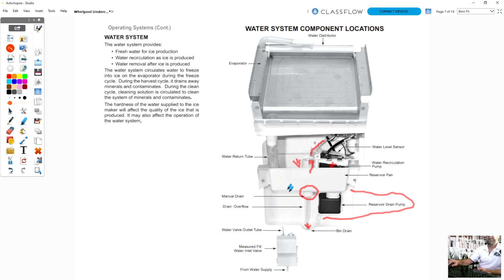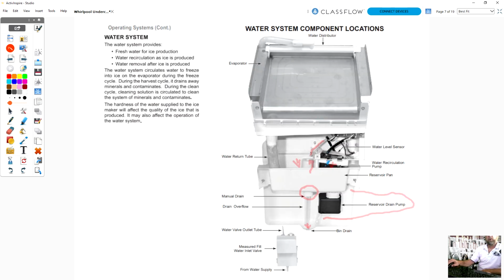If you're going to do any service to this area, you're going to have to remove the cutter grid like they're showing you in this picture here. So if you have to do the circulation pump, you have to remove the reservoir. I think you can remove this pump motor just by twisting it and pulling it out and quickly unplugging it. The only thing is all the wiring's up here, so this pump's got a wire running behind the reservoir and coming up to behind the evaporator. So on top of the recirculation pump was our water level sensor. That's located in this area here, and I'll show you a better picture of that as well. And that's now also a new component besides the drain pump.